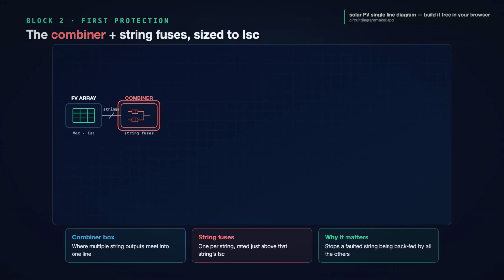On the single-line diagram, it is a small fuse symbol on each incoming string, feeding one combined line out. Fuses rated to the string current. Nothing exotic, but leave them off, and the drawing fails.